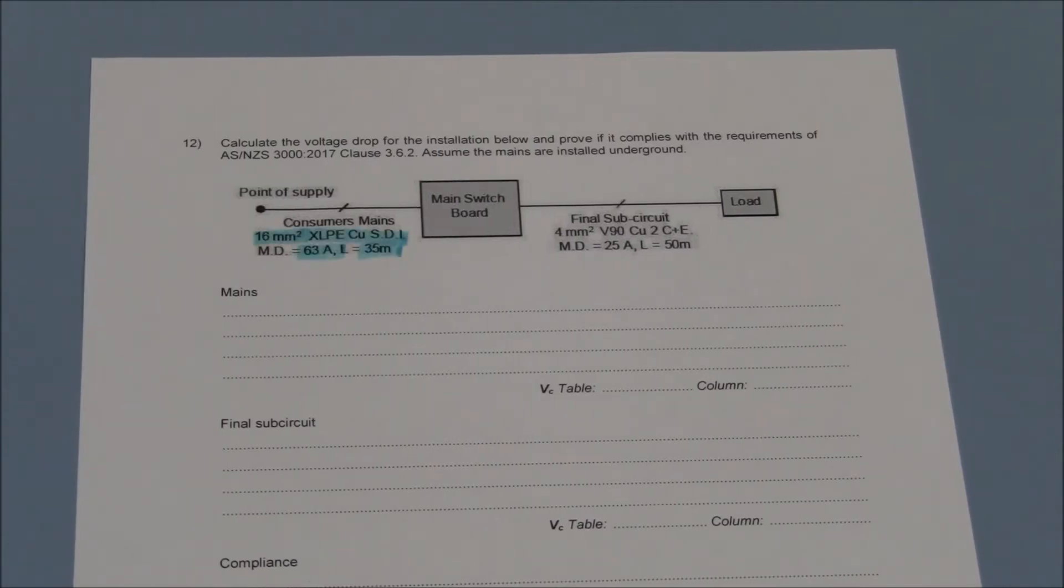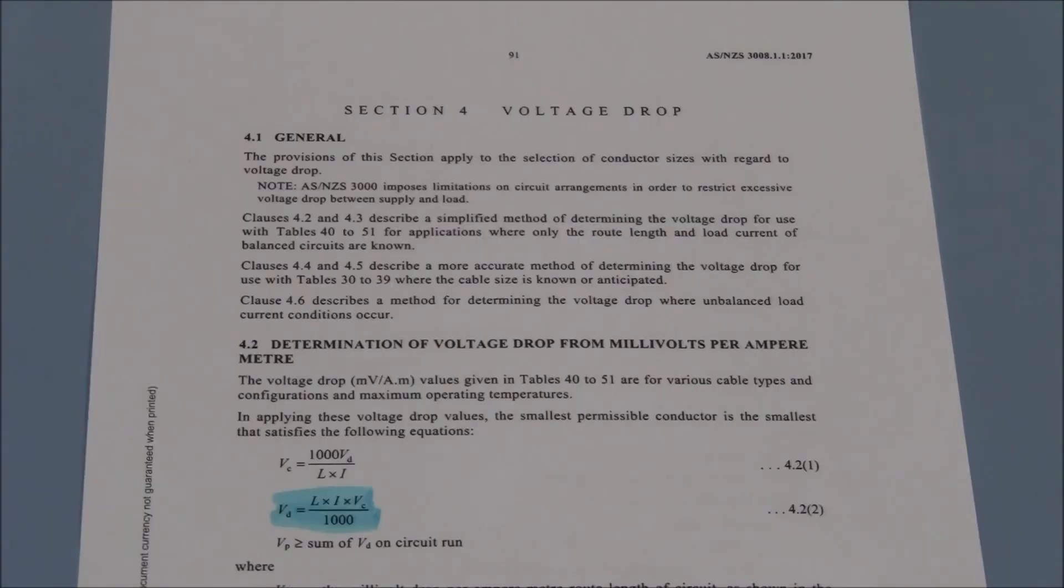The cable is a 16mm² SDI with copper conductors and XLPE or X90 insulation installed underground. The circuit is 35 metres long with a maximum demand of 63 amps. The voltage drop calculations are listed in section 4 of AS3008.